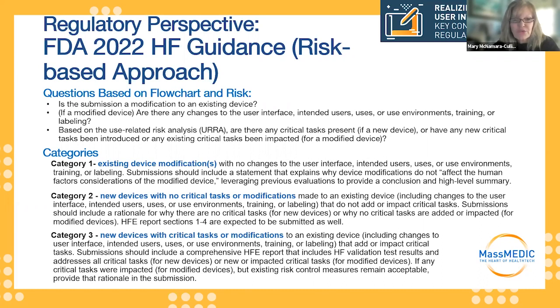So I'll just quickly go through. The first category would be for an existing device modification with no changes to the user interface, users, or use environments. So basically what would be required here is simply a statement, right? A statement in your marketing submission that you have reviewed this information, followed FDA's decision tree, and providing a statement in your document.